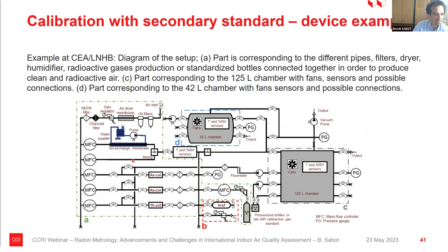So this is the radon chamber, the radioactive gas chamber I made in LNHB. What I can say is that when you want to develop such a system, the critical part is the green one here on the screen. It's the mixture of gas, and especially the choice of the mass flow controller you will use when you want to mix some gas lines. A very accurate system is quite important here. And then you can do any mixture.